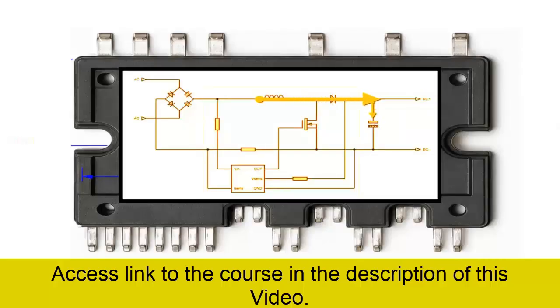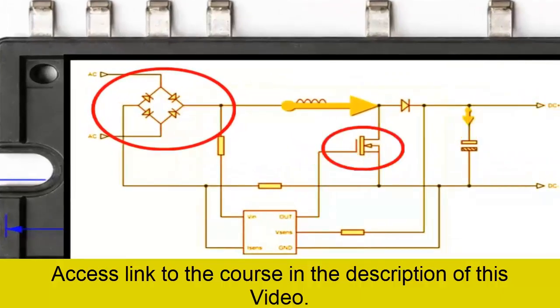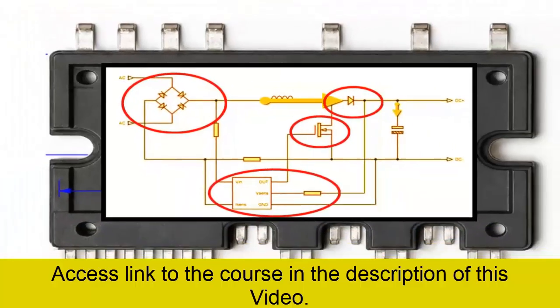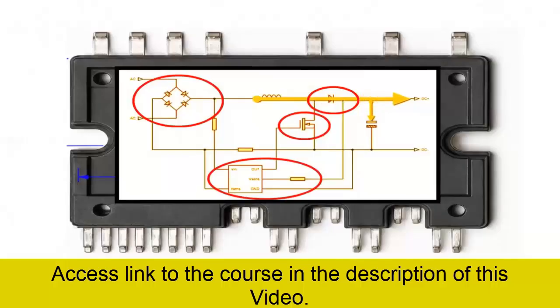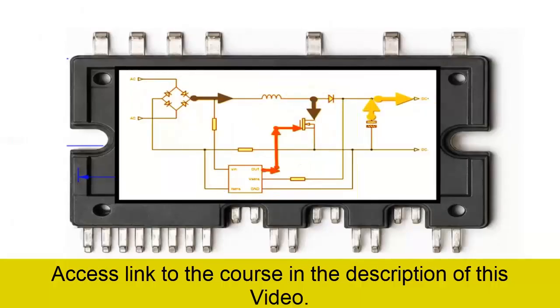It is essential to understand what the PFC circuit is and its function within the inverter system. In many modern electronic boards, the PFC circuit is integrated into a single intelligent power module, which internally incorporates components including the rectifier circuit, the Booster IGBT transistor, high-speed power diodes, and thermal protection sensors. Its main function is to convert the input alternating voltage into a high, stable, filtered DC voltage required to properly supply the IPM module of the inverter system.